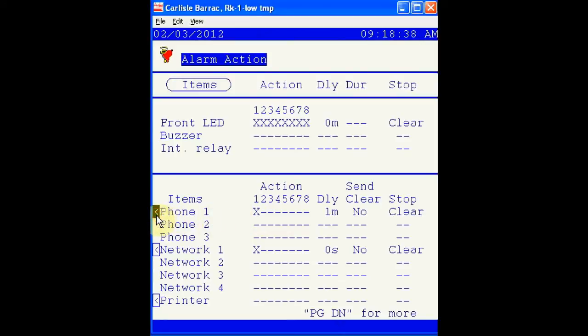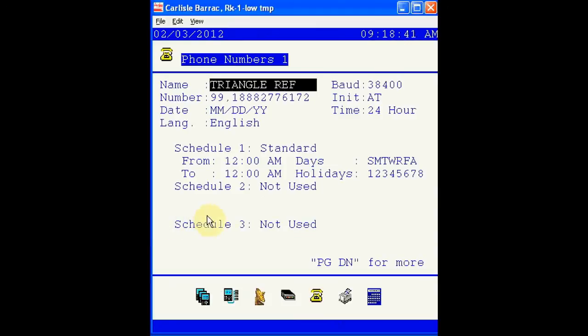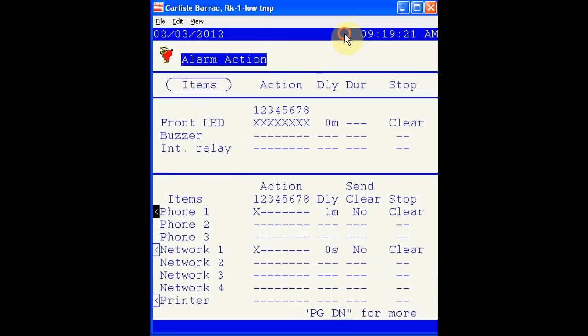Let's check the setup for the phone number 1. Here you can see it's been programmed to dial out to Triangle Refrigeration using this phone number. The person on site or the installer has determined that to send the alarm out to this number, they first must dial 99. The schedule has been set to standard, meaning the alarm will dial out any time during the day and any day during the week. If the schedule is not set from standard and left in the not used position, no alarms will dial out.